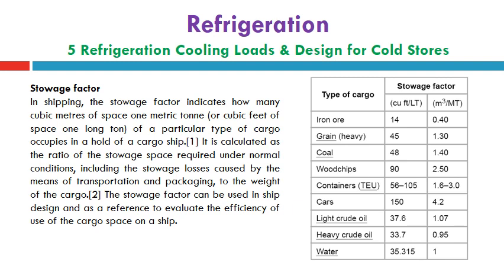The 1 ton occupies 0.95 cubic meter. So if we have apples, we have to get the stowage ratio: a ton of apples, how much space will it take in cubic meters. If we have meat, we have to check its stowage ratio. So the stowage ratio is a function of the water content of the product, and most food products have a water content ranging from at least 0.6 or 0.7 up to 99% or 100%. So the stowage ratio factor should be considered during the design and the space available for the capacity to be refrigerated and stored for a certain time.